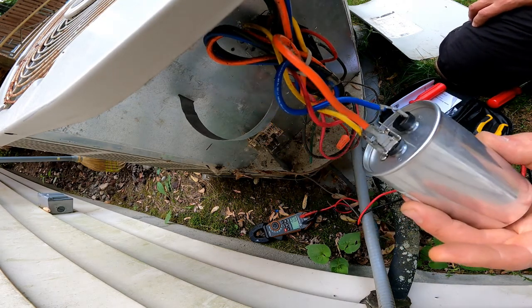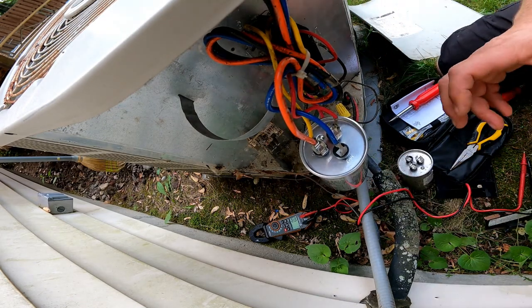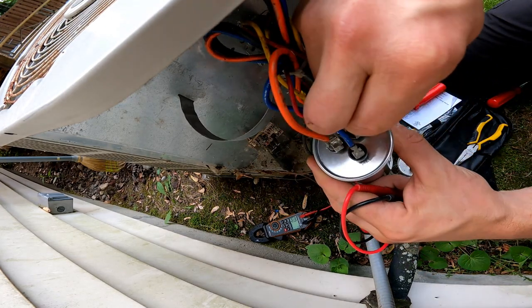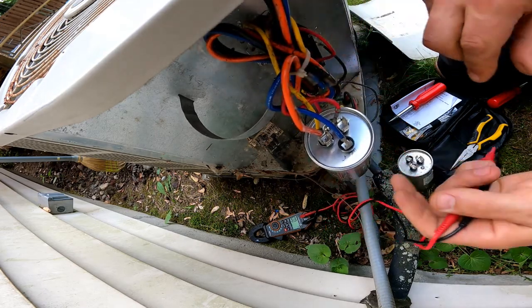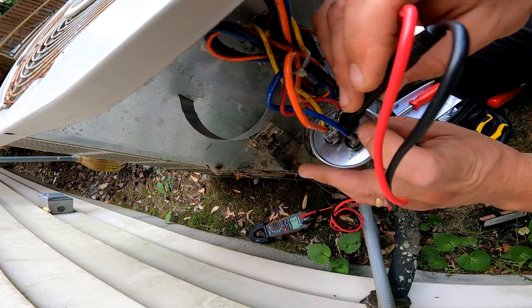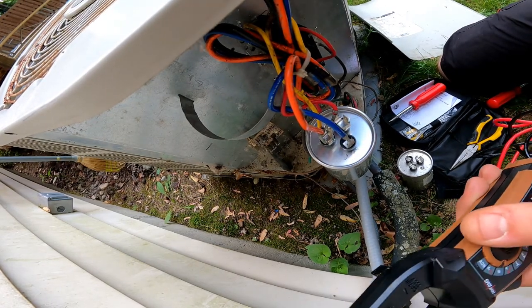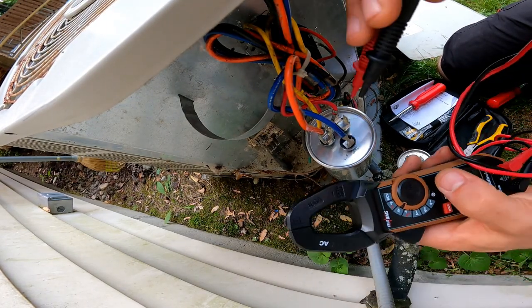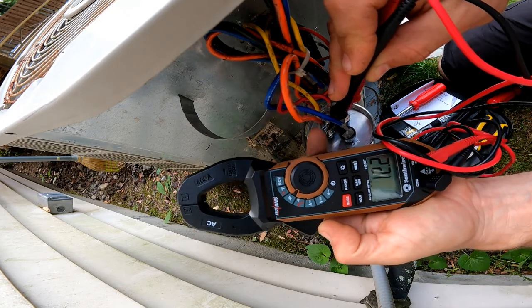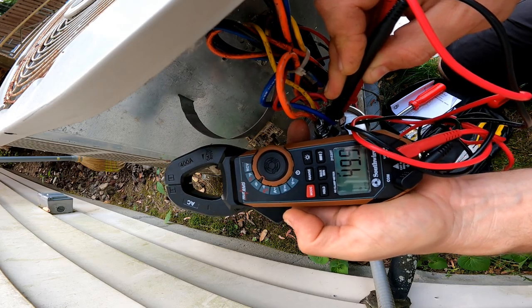So now we've got the new capacitor installed. Oh, maybe before I do that, let me just show you what I was expecting to see. So the Herm, let's just double check this, okay? So the Herm, and I'm just gonna go ahead and move this guy over here. Let's do this. Just want to give you kind of the full process here. I'm gonna go from this contact to this contact. All right, 49.9, dude, that's what I'm expecting to see.